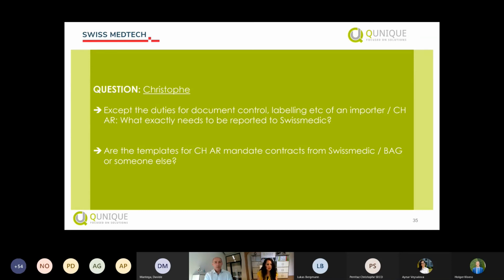Christophe, this question is for you. Except the duties for document control, labeling, etc. of an importer, Swiss authorized representative. What exactly needs to be reported to Swissmedic? Well, I'm sorry, but I'll hand over. It would be useful if Daniel would add this up. But basically, everything which would need to be registered in EUDAMED, and everything is registered in Article 33, I think, of the MDR. So everything would need to be provided to Swissmedic. But maybe Daniel would be more specific on this. No, it's perfect what you say. It's the same duties as to EUDAMED, but in Switzerland it is actually to Swissmedic, to the Swiss authority.